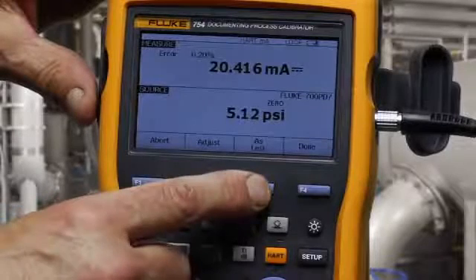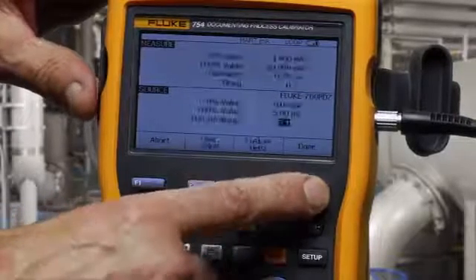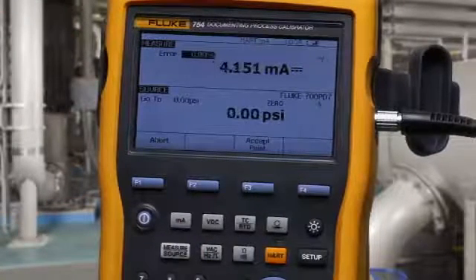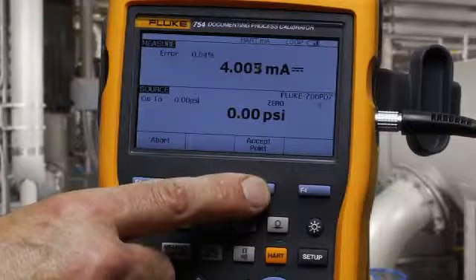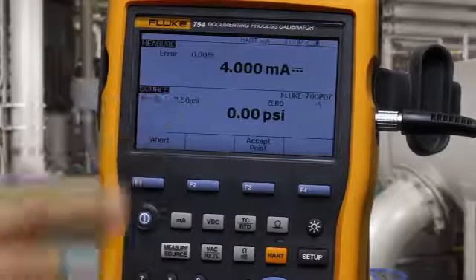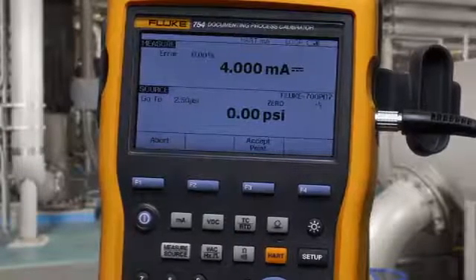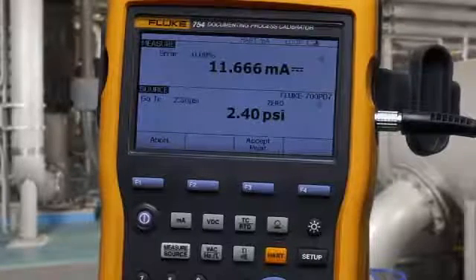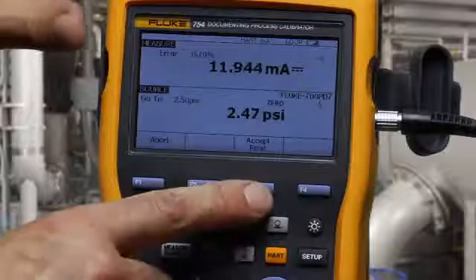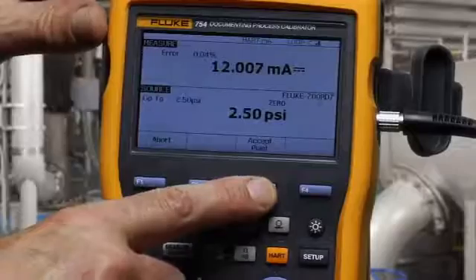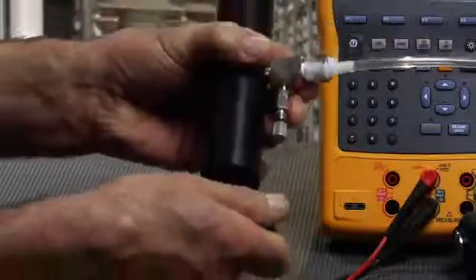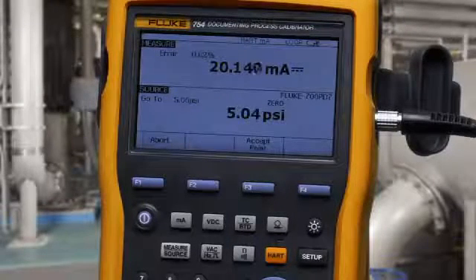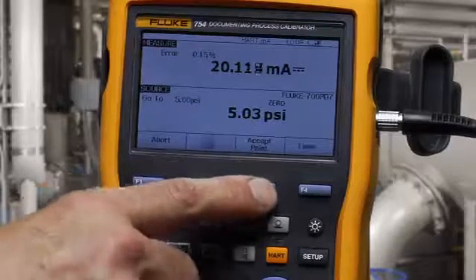Now, once the adjustment is complete, select as left and repeat the test and confirm that the adjustment was successful. Apply the zero percent value, 50%, and then 100% 5 PSI. Test is complete.